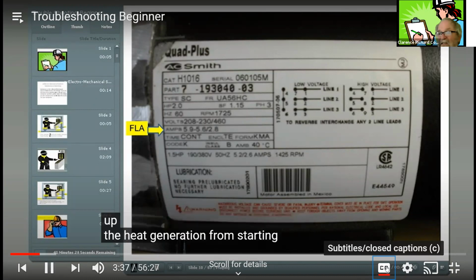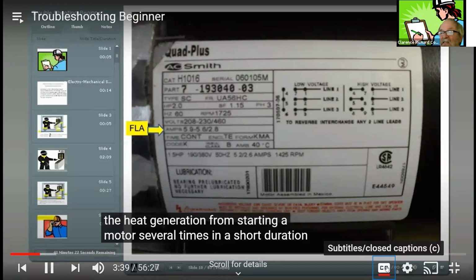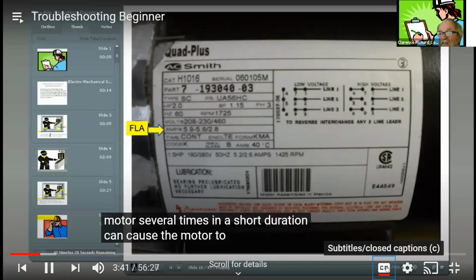The heat generation from starting a motor several times in a short duration can cause the motor to burn up. Starting and stopping motors gets to be a pain in the butt, especially with big fan motors, 100 horsepower, 200 horsepower. You don't want to be starting and stopping those. There's a lot of internal heat happening there, and you can ruin a big motor that way.